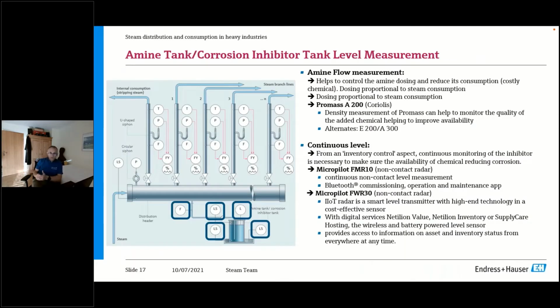So when we go further down the line, we go into the amine tank. This is for corrosion inhibition. So it may be at a different point in your system. Here you want to do some inventory management, and in doing so, you need some level measurements and you need a flow measurement. For the flow measurement, typically you're talking about small amounts. So here we recommend, because that chemical is typically expensive, using a Coriolis meter for best accuracy. And those are available also for small line sizes. So 1 millimeter, 2 millimeters, that's easily done.